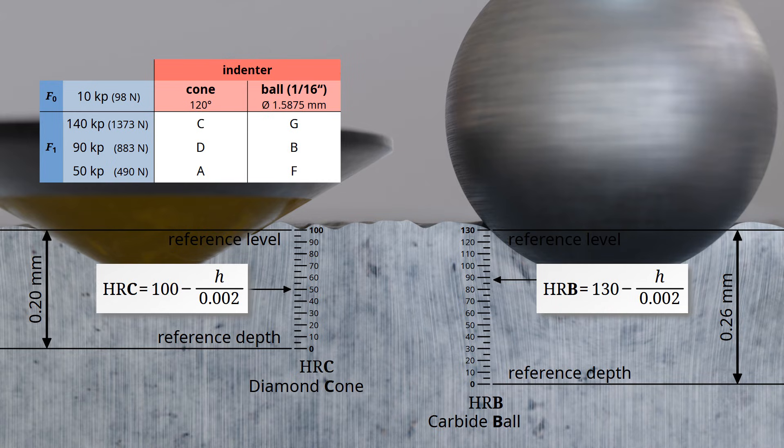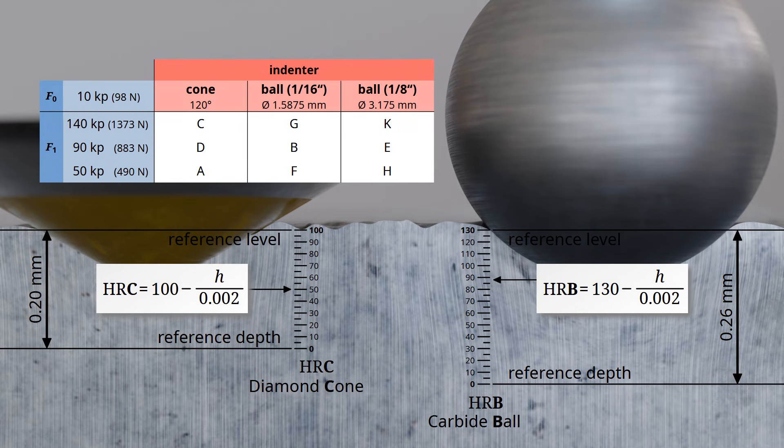In special scales, cemented carbide balls with a diameter of 1/8th of an inch can also be used as indenters. The table provides an overview of the common Rockwell scales. The hardness values determined with different scales are generally not comparable. Additionally, the hardness value determined using a specific scale must fall within a certain range. If the value falls outside of this range, the scale must be changed, as the indenter has either penetrated too deeply or not deeply enough into the material.